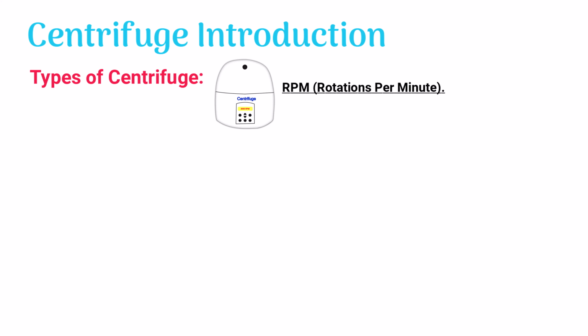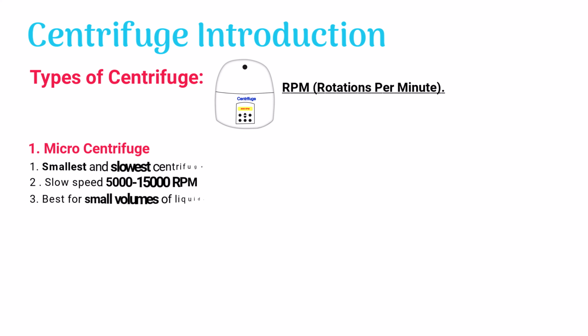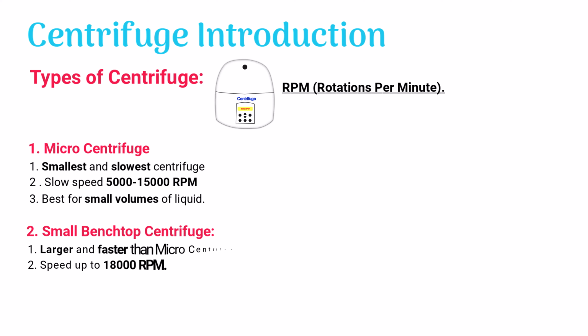There are different types of centrifuge based on their speeds, like the microcentrifuge. It is the smallest and slowest type of centrifuge. It spins at a slow speed ranging from 5000 to 15,000 rpm. It is best for separating small volumes of liquid. Small benchtop centrifuge. It is larger and faster than the microcentrifuge. It can rotate at a pace of up to 18,000 rpm.